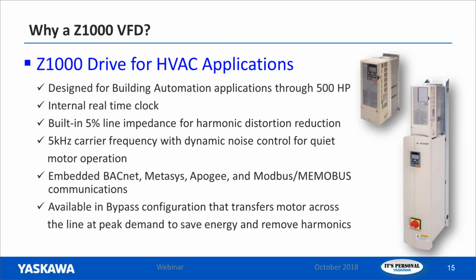So we covered why a VFD. How about why a Z1000 drive? Well, the Z1000 drive was designed specifically for HVAC applications. We're not taking a general purpose drive that gets used on rock crushers and conveyors and elevators and escalators and saying, hey, this will spin a fan too. No, this was designed specifically for HVAC applications. So the Z1000 drive, we've got it designed through 500 horsepower, has a built-in real-time clock.